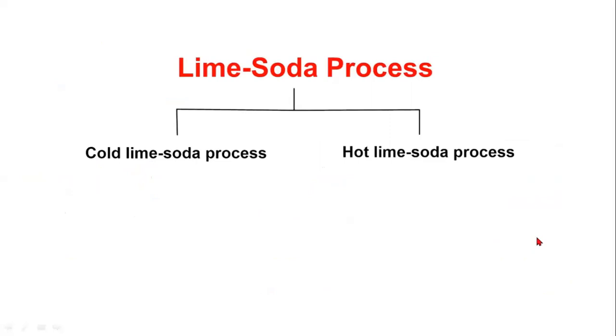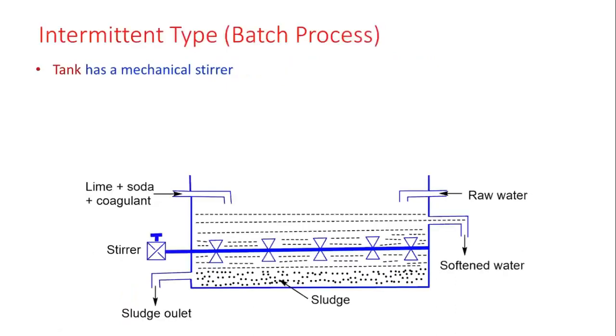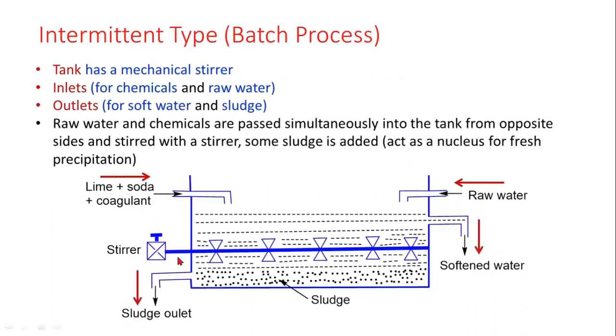The lime soda process has two categories: the cold lime soda process and the hot lime soda process. The cold lime soda process uses the batch intermittent or continuous method. The hot lime soda uses the continuous method. In the cold process, there is a mechanical stirrer that rotates. Lime, soda, and coagulants are added on one side, raw water enters from the other side, the sludge settles below, and soft water exits.